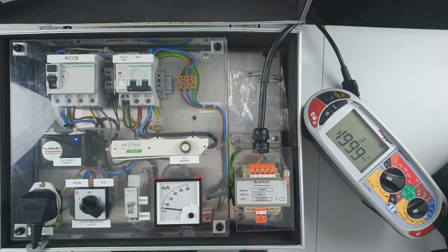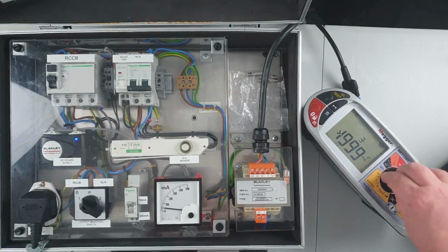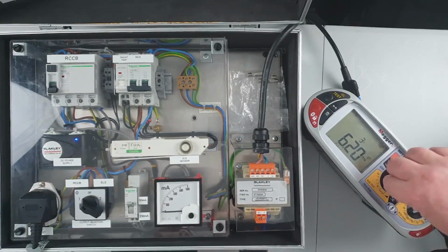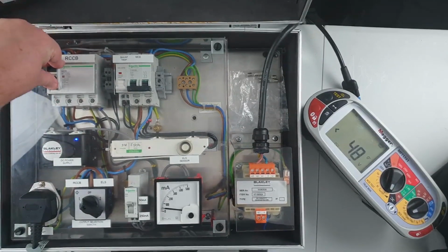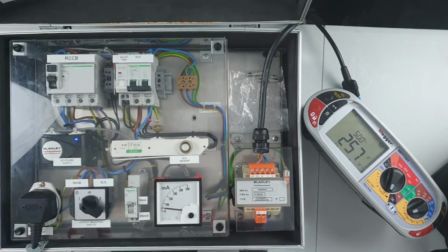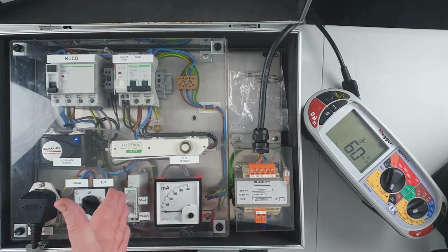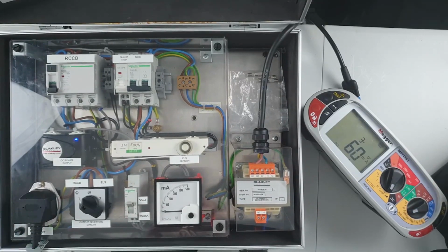No trip. Okay, let's go up again. Let's go to times 100. So 100 milliamp test. So it's tripping on the 100 milliamp. If I now do the ramp, what we would expect to be 30 milliamp or less is now 60 milliamps. So that's a huge difference. It requires 60 milliamps of leakage current for this 30 milliamp device to operate, purely because of 50 milliamp of DC leakage into the system.